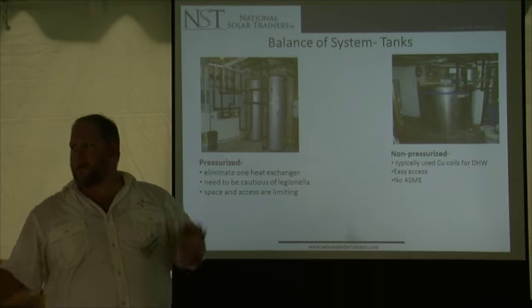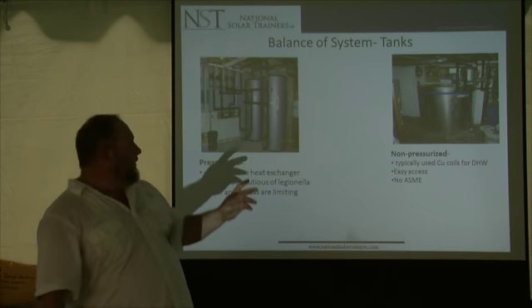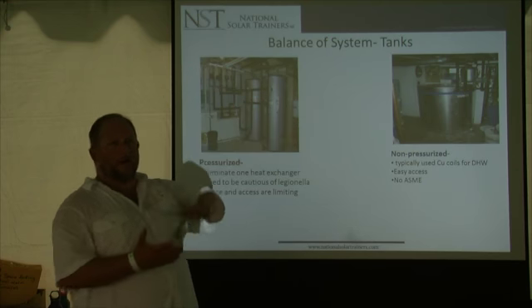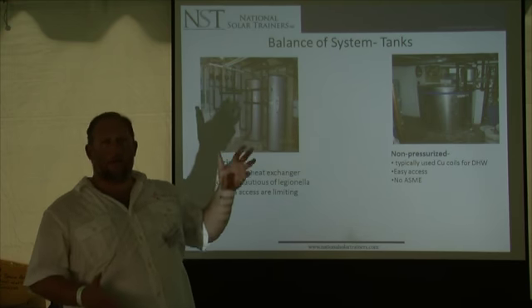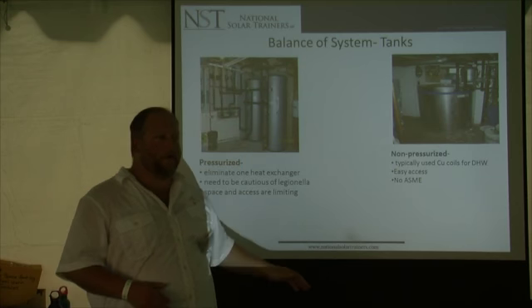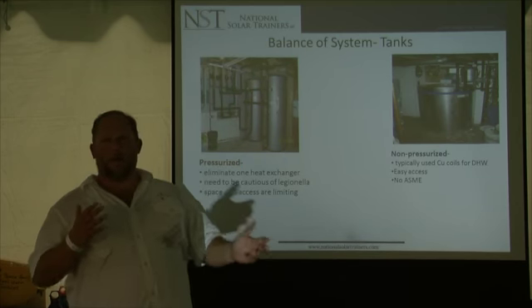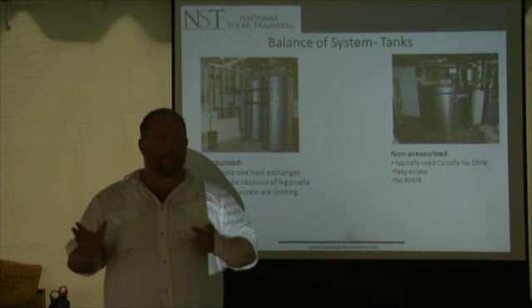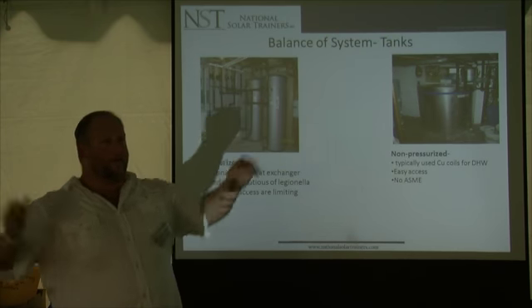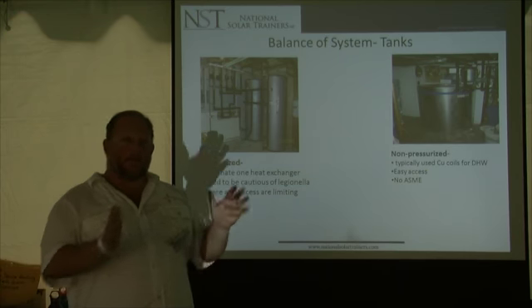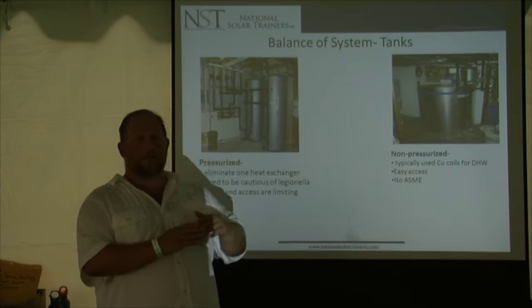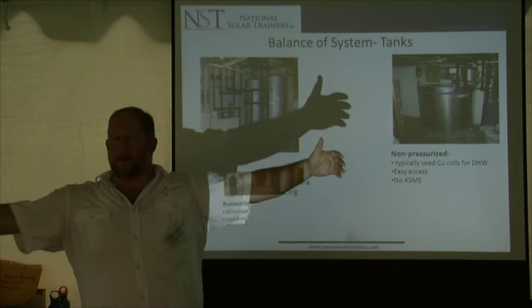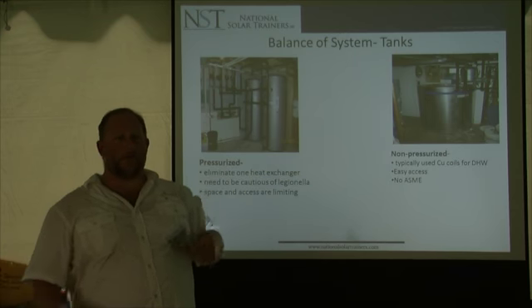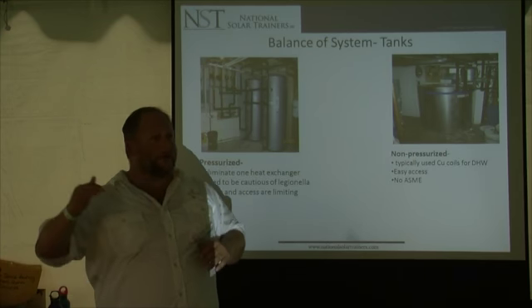Okay, so we need to put those BTUs in a tank. Well, the more BTUs I put into this tank, the hotter the temperature. The hotter the temperature is, the lower the efficiency of the collectors. So it's a very fine line between a tank that's big enough and a tank that's too big. If it's too small, the tank temperature is going to skyrocket, my collector efficiency goes down. If it's too big, then my return on investment goes down because I'm never able to achieve the necessary temperatures in the tank.